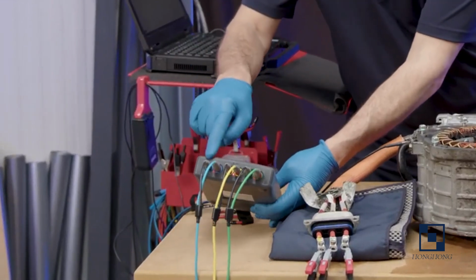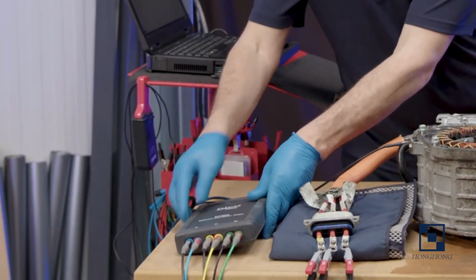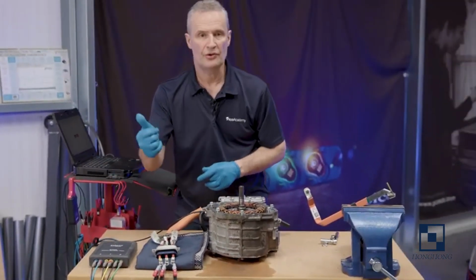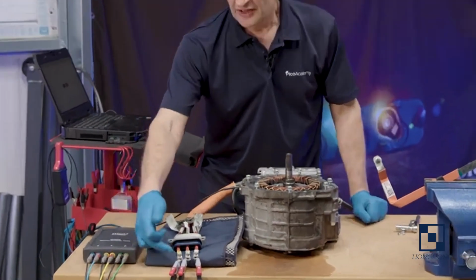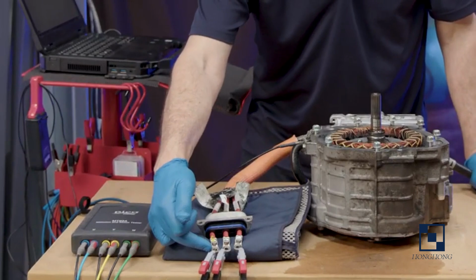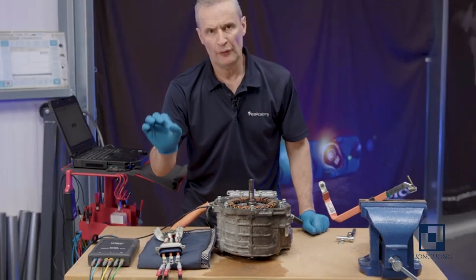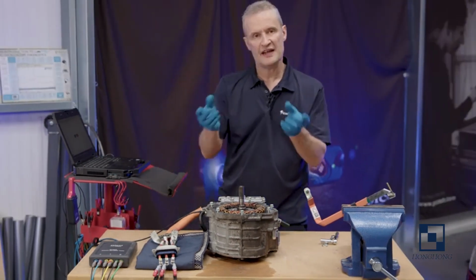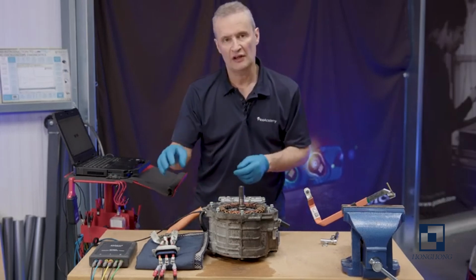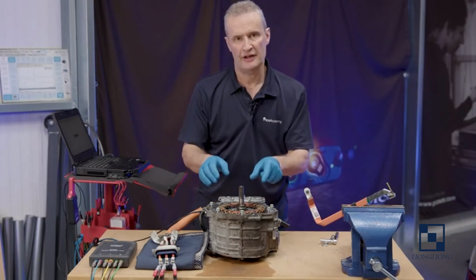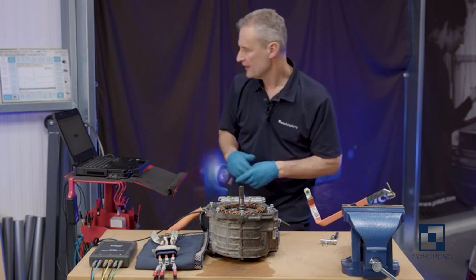Now here's the real beauty: we're measuring each phase in one measurement, so we'll be able to do U, V and W. So you see here that we have the Kelvin clips attached to each phase. We measure from point to point, so the lead is taken out of the resistance value, and we only obtain the resistance of the winding, so it is a highly accurate measurement.